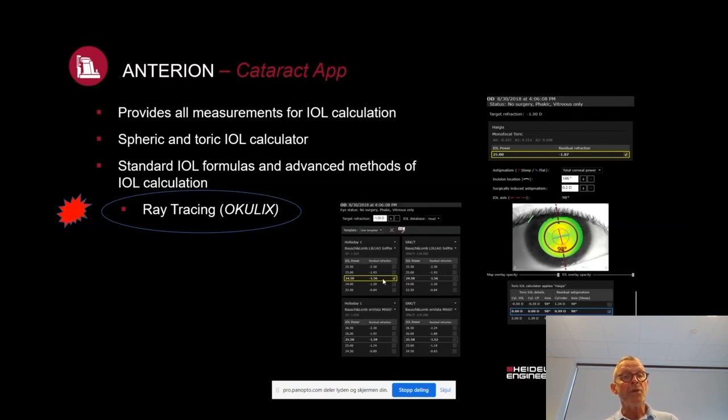I want to pinpoint that this instrument gives you easy access to ray tracing, combining anterior OCT measurements with OKULIX ray tracing software. This opens up a new perspective in biometry. From a theoretical point of view, individual measurements for individual planning should be the way to go. But until recently, this has been hindered by having to use different instruments to collect all the data, and the noise from all the instruments really destroys the potential of ray tracing technology.